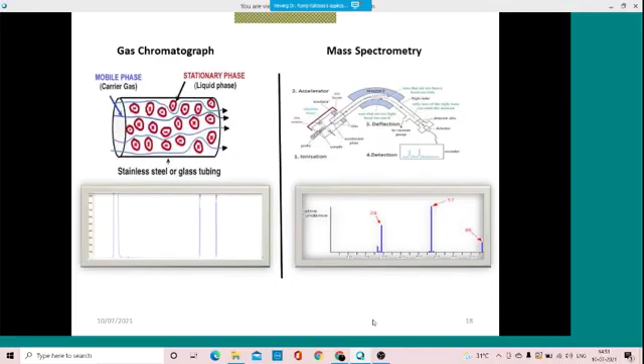This is what the equipment looks like. This is the column where our breath sample would travel and reach the detector. Here is where the breath sample is injected. And for this breath sample to travel towards the detector, we need some carrier gas, that is nitrogen. Nitrogen is an inert gas, so it helps the breath sample to travel through the column and reach the detector.